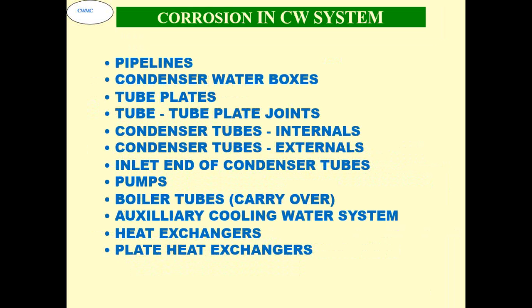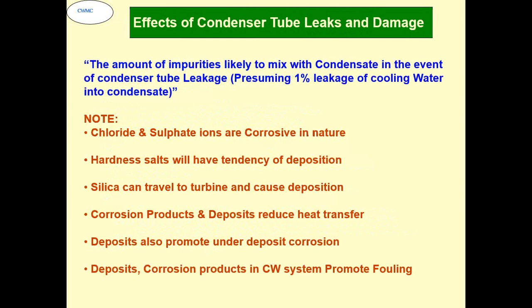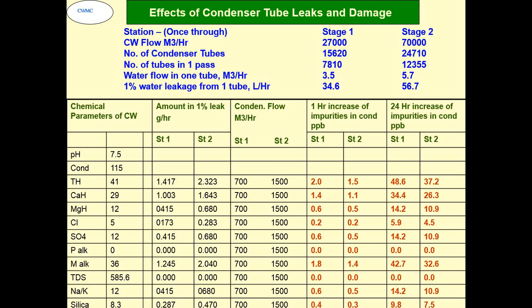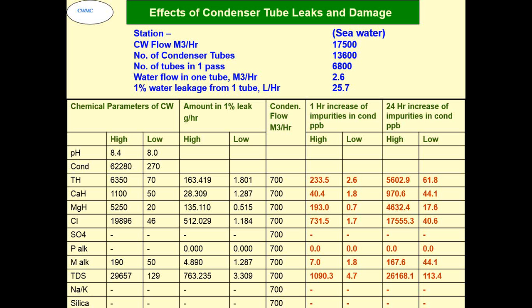Systems which are generally affected are pipelines, condenser water boxes, tube plate joint, condenser tubes internals, condenser tubes external, inlet end of condenser tube, pumps, boiler tubes, carryover from the condenser, auxiliary cooling water system, heat exchanger plate, etc. Now this is typically what you see in a power plant, the impact of cooling water or condenser tube leakage. This is the normal river water case, and we have calculated the different amounts of chemicals which can go to the boiler, which has high purity water as the treatment. These are the impurities which go there in a 24-hour or 1-hour period. If you go to the seawater system, you can see a drastic change, and immediately we have to take corrective action once the problem of condenser tube leakage is observed.